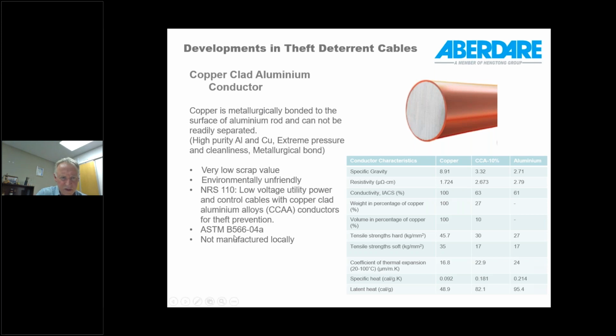The metal requirements for this conductor metal are also well described in this ASTM standard B566, and all these conductors are imported. But currently I'm not aware of any cable that is physically made with these conductors and imported in this country, except for non-compliant cables, wiring cables in particular, flat twin and earth, which is brought in from overseas. We've seen imports from China where these cables come in and on the surface look to be compliant, but if you look at resistance values and current carrying capacities, these cables are way below the standard and can lead to fires and so on.